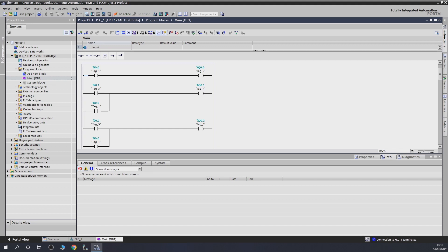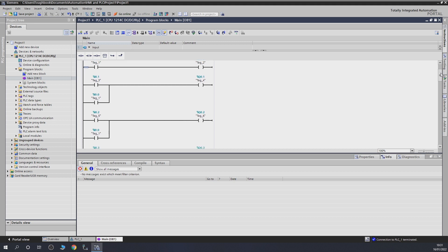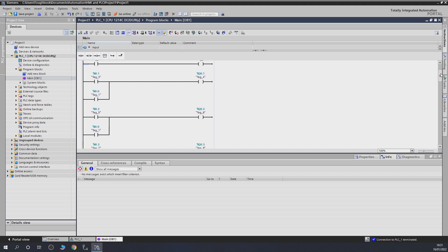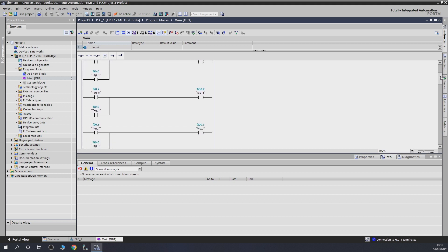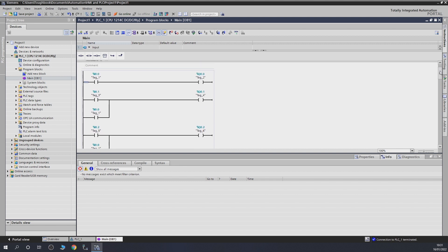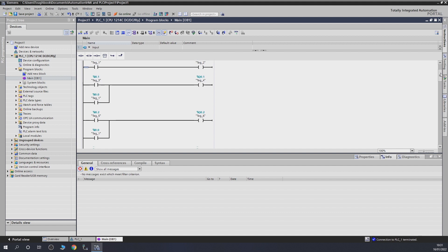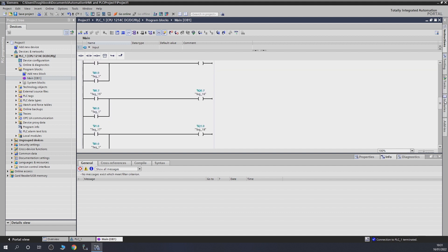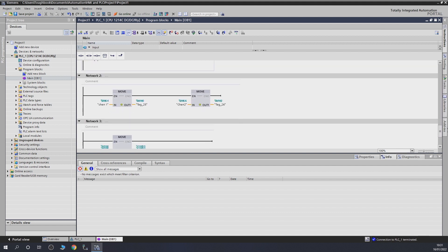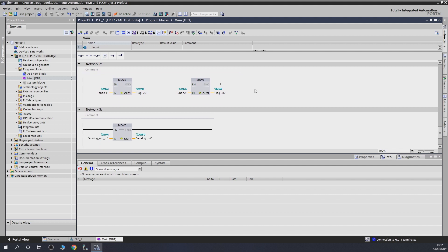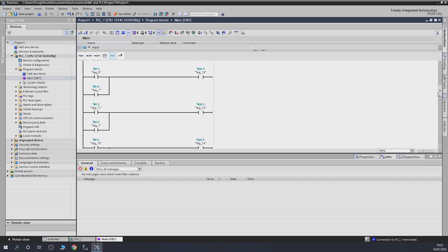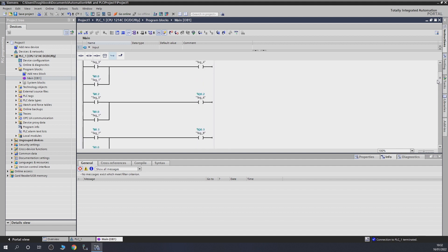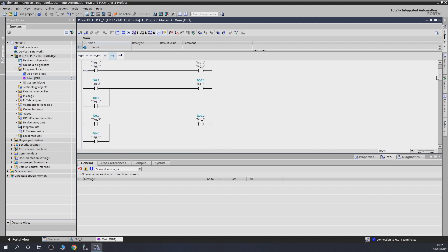I'll show you the program. So this is the program that we've done. So what I have in here is I will be activating all the digital inputs. So each digital input will reactivate in some form of a output and my digital input zero will activate all of them as well for me to test all the relay outputs for this particular program. So as you can see, I just created like a small program in there, test all the inputs and outputs. And as you can see in here, there's my network for the analog inputs as well. So and there's my analog output, which is going to be sending signal to these guys to make sure they are reading correctly.